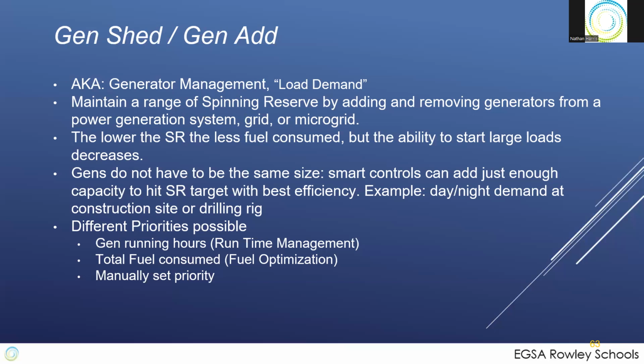And you add and subtract generators to maintain a condition, if you will, a spinning reserve condition. Typically with a 5-gen system, let's say you have an outage, you send a start signal to all 5. Hopefully they all start. If they don't, you're still okay. You only need 3 to run. Once you get 3 on the bus, maybe even all 5 on the bus, you maybe wait half an hour to get them nice and warm. Then you start taking off the unnecessary generators to save fuel and just run on the 3 you need, keeping the other 2 in standby, if you will, cold standby or operating reserve. So that's Gen Shed Gen Add.